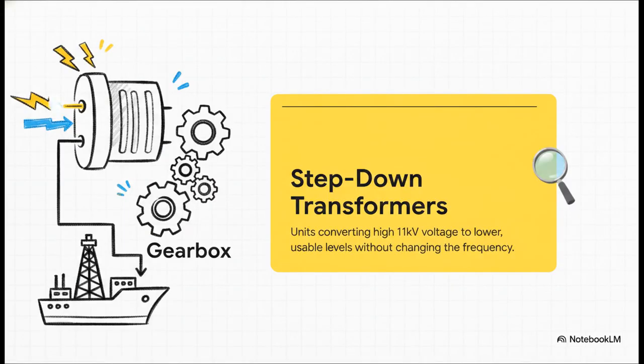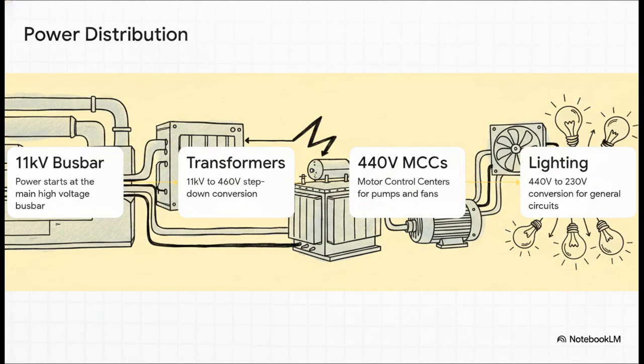And that's exactly where step-down transformers come into play. You can think of these 3200 kVA, 11 kV to 460V units as electrical gearboxes. They take that roaring high voltage from the main distribution system and literally step it down to a lower, safer, and much more usable voltage, all without changing the electrical frequency. Because remember, the vast majority of the equipment aboard simply isn't designed to run off 11 kV. It would be fried instantly. Let's move along and see how this builds.